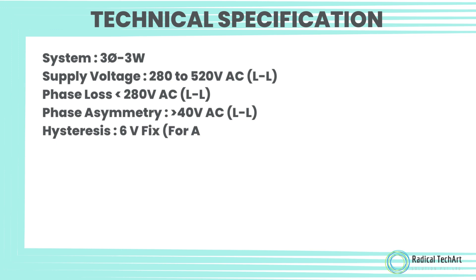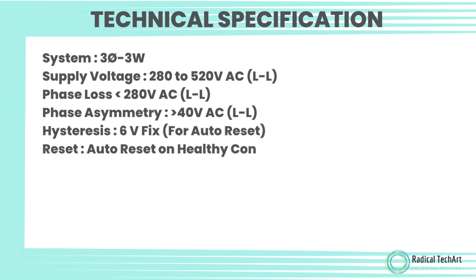Phase loss: 280 volt AC line to line. Phase asymmetry: 40 volt AC line to line. Hysteresis: 6 volt fixed for auto reset.